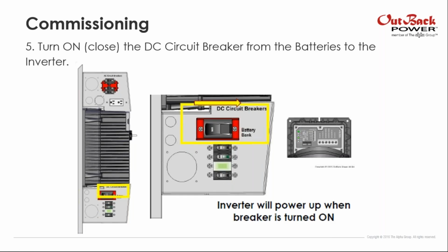Then you have to turn on the DC circuit breaker from the batteries to the inverter. It's the big one. You will recognize it easily because not only is it the big one, but it has a red cover around it. So as I said before, this breaker is 175 amps for the 48 models and 250 for the 24-volt models. When you turn on this breaker, your inverter will power up. When you power up the inverter, you will start to hear the noise of the fan. That's when you see that your inverter is working. And you will see that it will start to light the LED indicators.